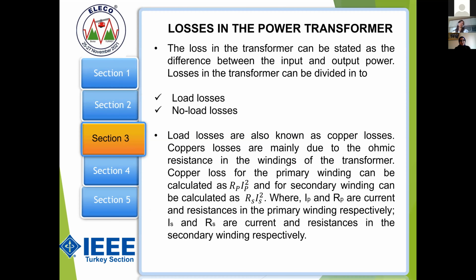So we all know that the losses in the transformer can be stated as the difference between the power of the input and output. What power we are giving to the transformer and what we are taking out is the difference between the power of input and output. And losses in the transformer can be divided into two major losses. We have others as well, like stray losses, but the major losses of the transformer are load losses and no load losses.